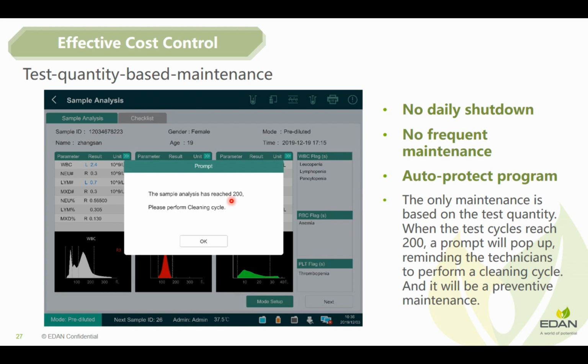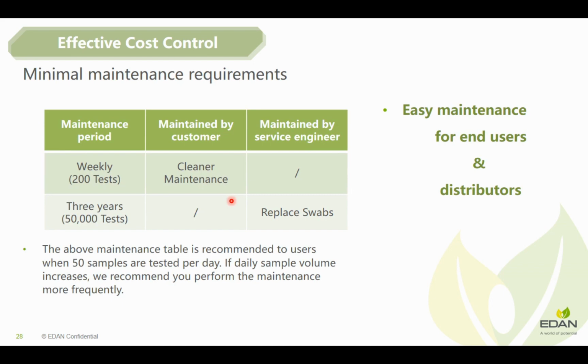What about for the distributors? Barely any. Let's check the maintenance table. For end users, the cleaning cycle is estimated and weekly based, depending on the daily volume. For engineers, it's around once every 3 years that you will need to replace the swabs. But such frequency is projected based on 50 tests per day. If your daily volume is lower or higher, you should change the frequency proportionally.